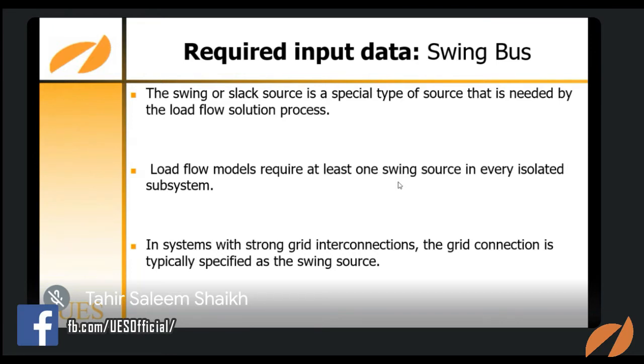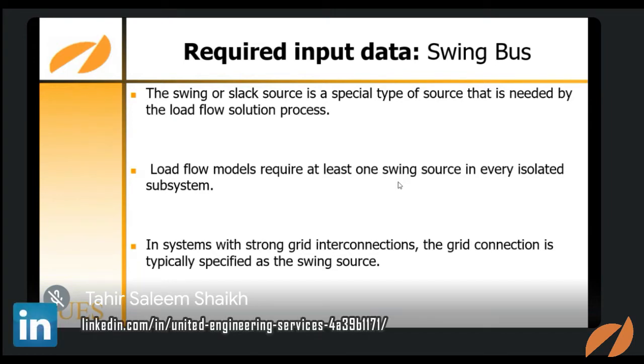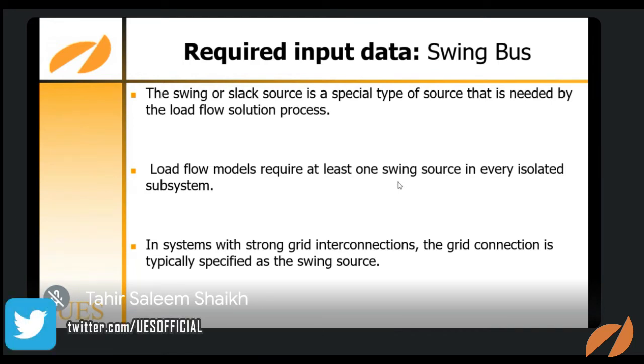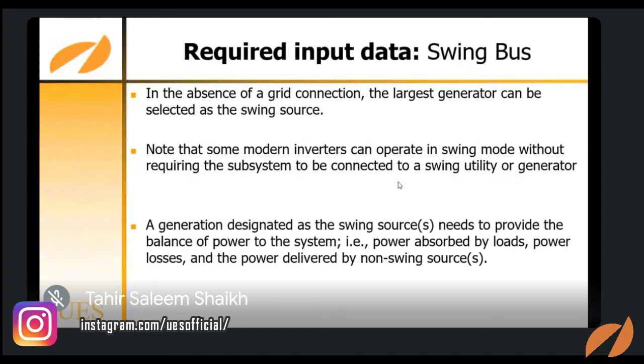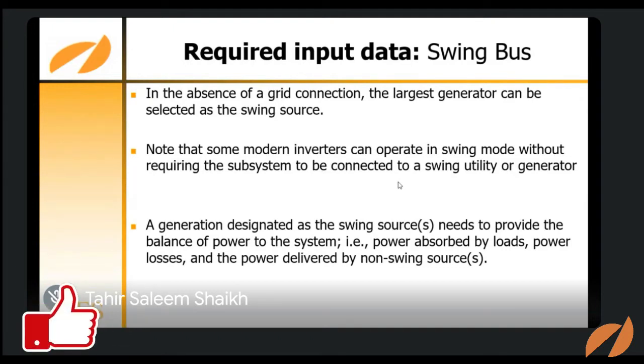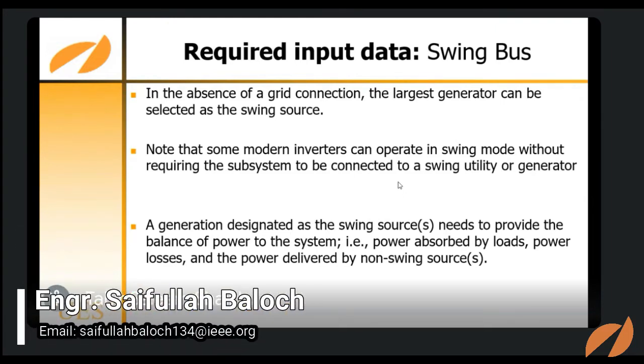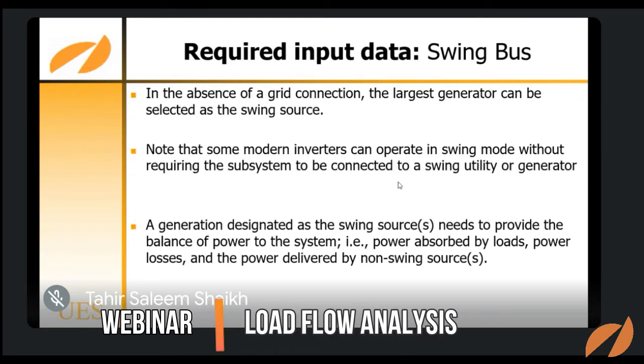If the load is rated at 1 megawatt, and after some time in the future it grows and demands 2 megawatt, then this bus is responsible to increase the power generation, give the supply, and balance the supply and demand of this system. Most of the time the generators connected in a commercial or industrial power system are operated in swing mode: if the load is increasing, the generator starts to increase its rpm or any electrical parameter according to the setting and parameters of that generator, and it will start to supply that power.